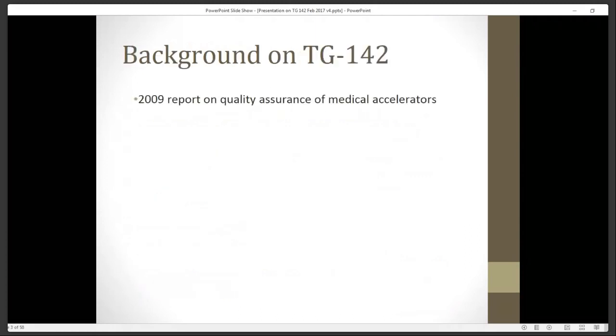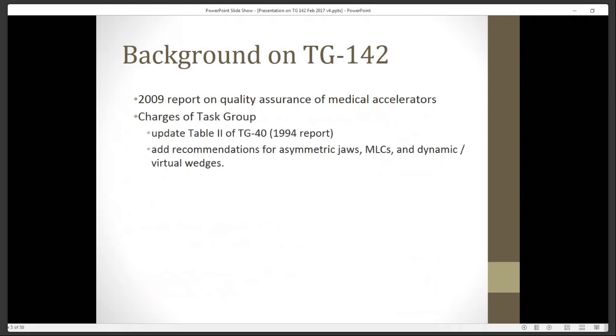A little bit of background: this report came out in 2009 and is basically on the quality assurance of medical accelerators. At that time, it was an update to a prior report, TG40 from 1994. The task group was charged to update the table from TG40 and add recommendations for things that had been developed along the way, including asymmetric jaws, MLCs, and dynamic virtual wedges.